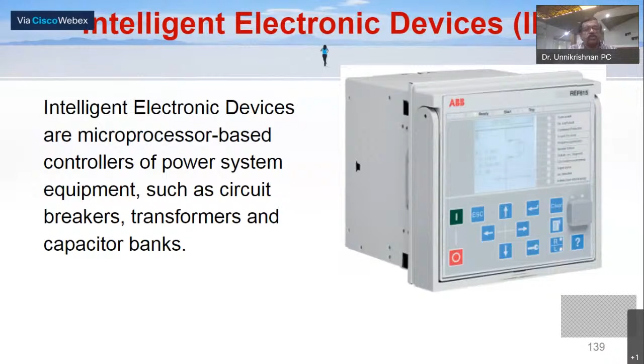Basically, IEDs are microprocessor-based controllers of power system equipment, such as breakers, transformers, capacitor banks, etc. They have a high scanning rate. IEDs are installed in substations basically for automation in data collection, improving the data integration, monitoring, and control. Then data sampling synchronization is the major advantage of IEDs. That is, two IEDs located in different parts of a substation can be synchronized. So they'll be operating with the same clock.